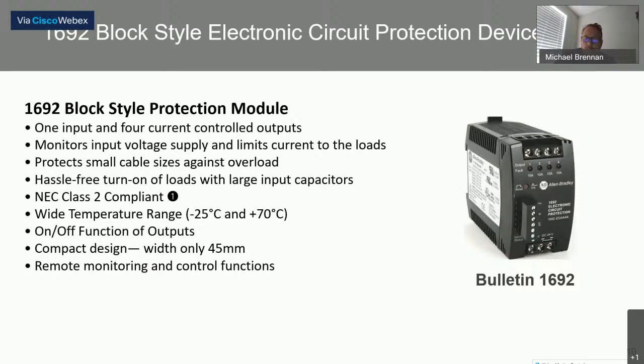So this unit's only 45 millimeters. If you thought about our previous device where we had 11 circuits and it was 271 millimeters, 2 of these would give you 8 circuits, and that would only be 90 millimeters in width. So we could utilize the block style and have more circuit capability. We'd have better annunciation, fault diagnostics without additional components back to the PLC, and we'd have a smaller space. So you can see where the block would make a lot of sense.